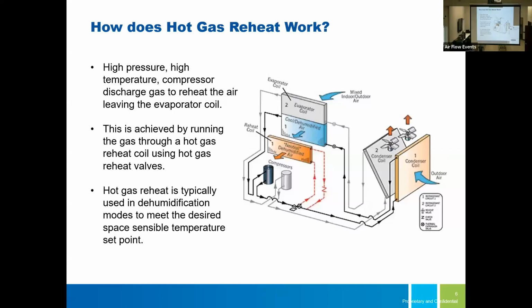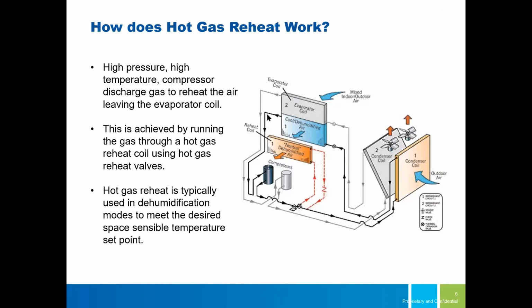Then aside from that, I'm just wondering, in this picture, is the hot gas reheat condenser coil a dedicated coil? Yes, it is a dedicated, separate coil. You see in this picture, that orange device, the hot gas line coming off this compressor, so there's a separate coil there in the system.